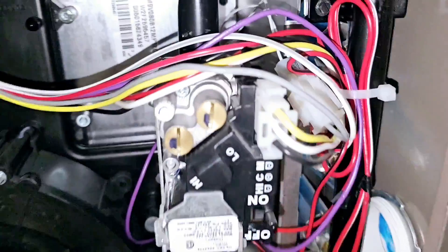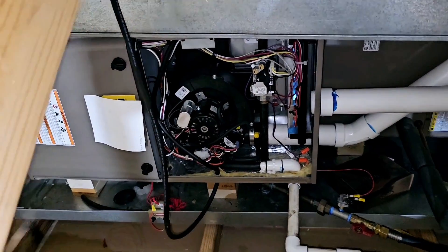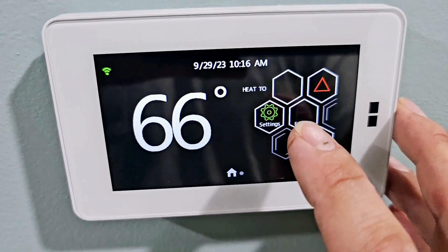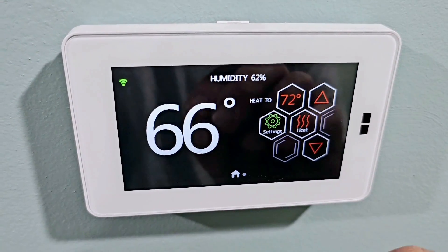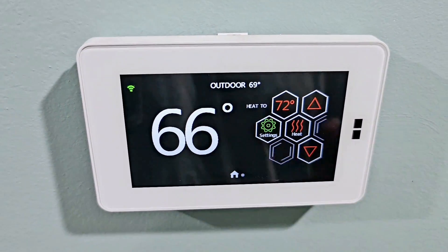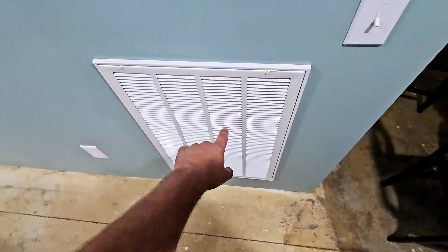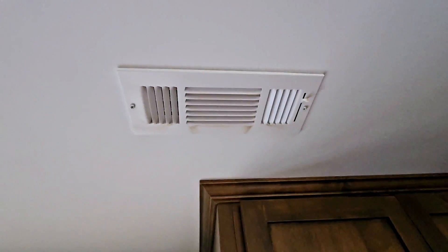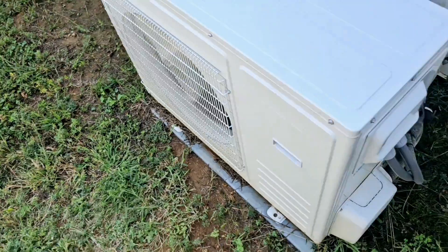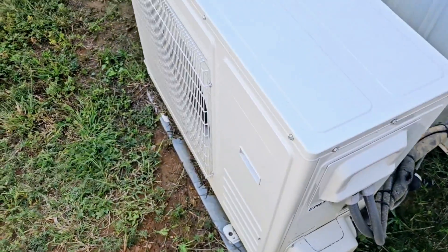Now that went to low stage — you've got a two-stage gas valve. If you don't know how to set gas pressure for two-stage propane, I'll put a link to a video so you can learn how. That's emergency heat. Now we're going to take it off emergency heat, put it on regular heat, and show you that the heat pump will turn on. The return grill is 20 by 30 — that gives us 600 square inches because you want 200 per ton. We've got 12 six-inch lines coming to four-by-12 ceiling vents, so that's 1,200 CFM. Outdoor unit kicked on in heat mode. Vapor line is warm — perfect, it's working as it should.